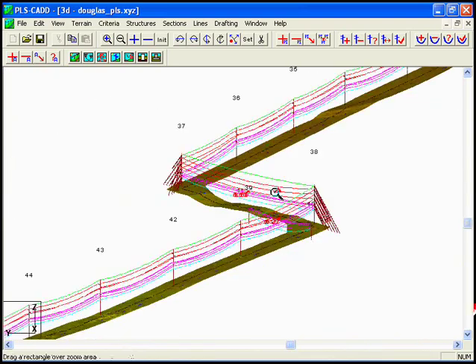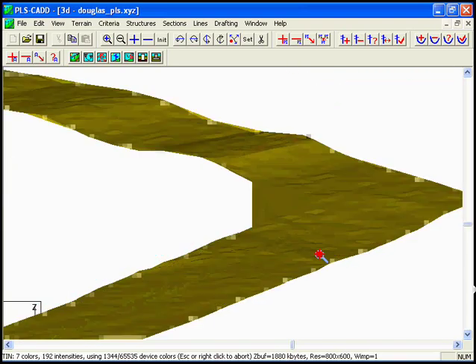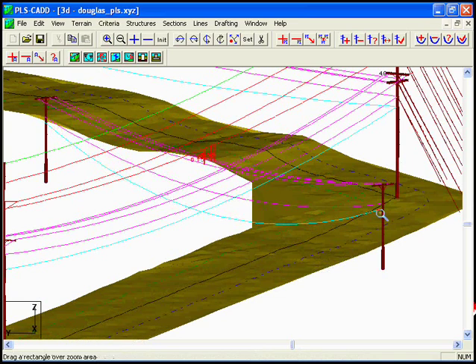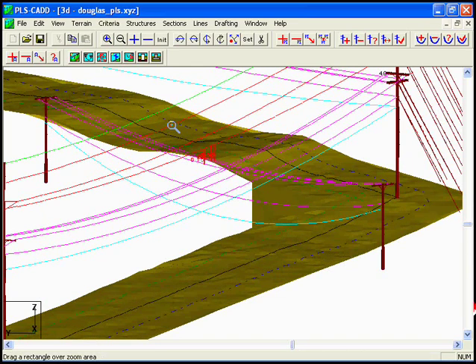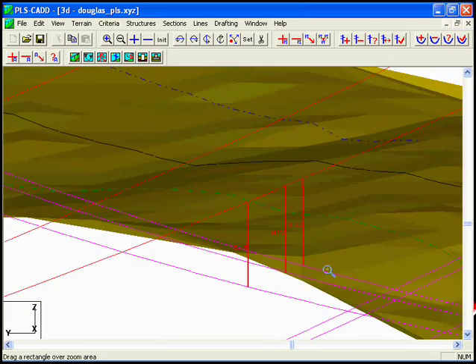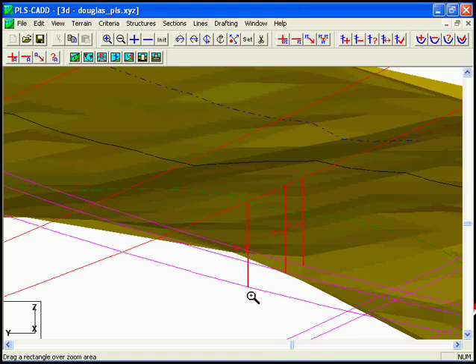Backing back out a little bit, we can move over here, and in our distribution crossing that we have going underneath this line, you can see that in this particular area right here, we have 6.15 minimum clearance between the lowest phase in this particular circuit of our distribution crossing.